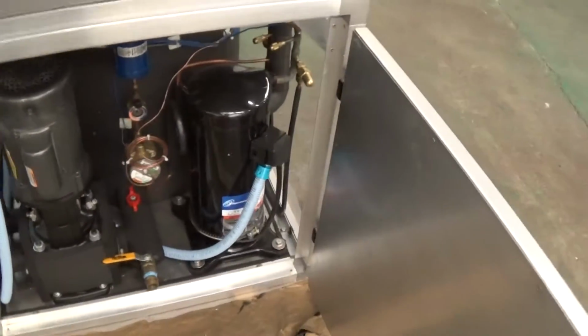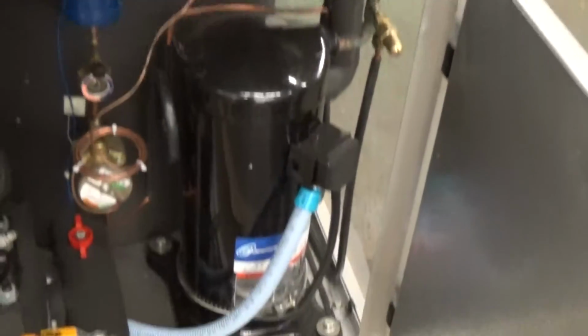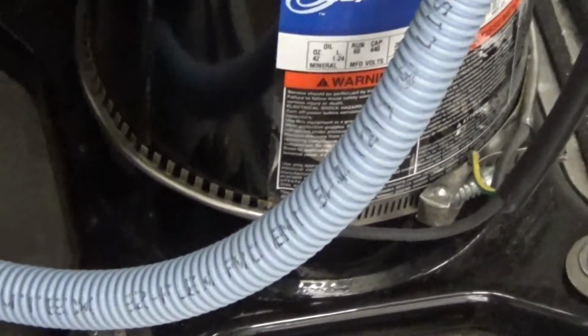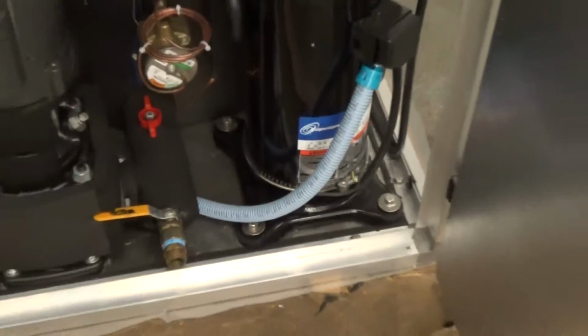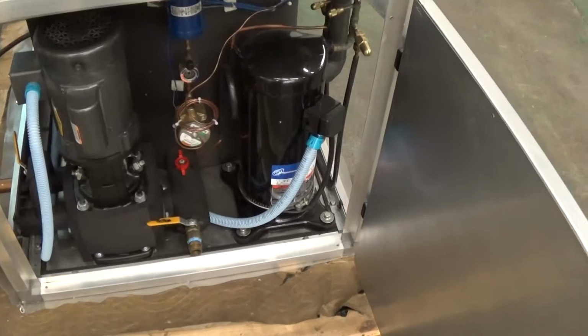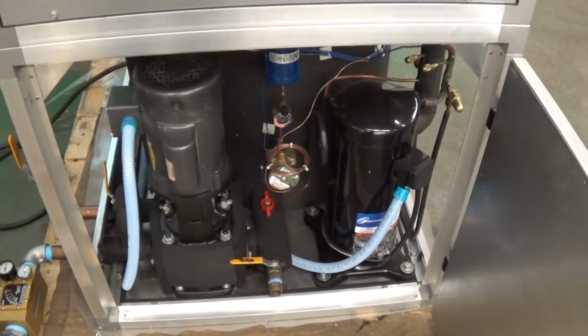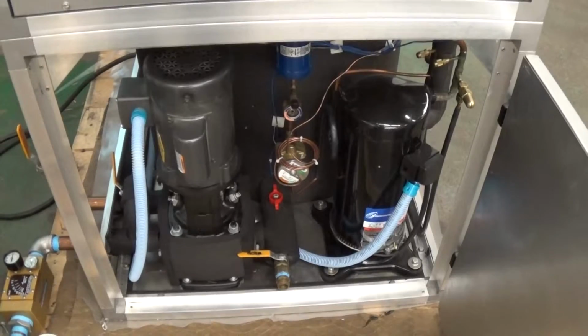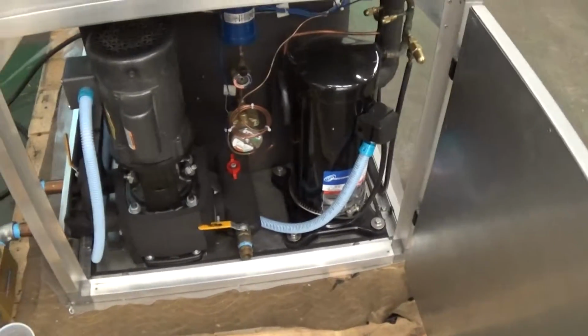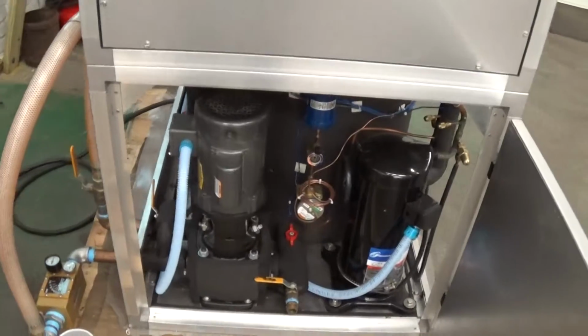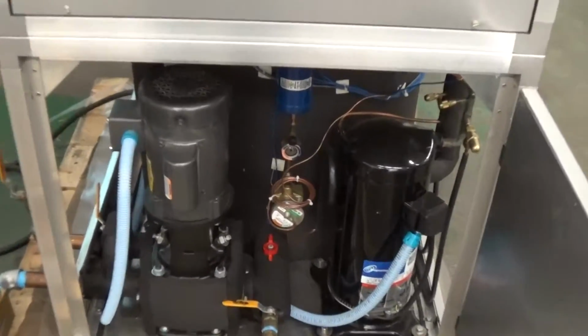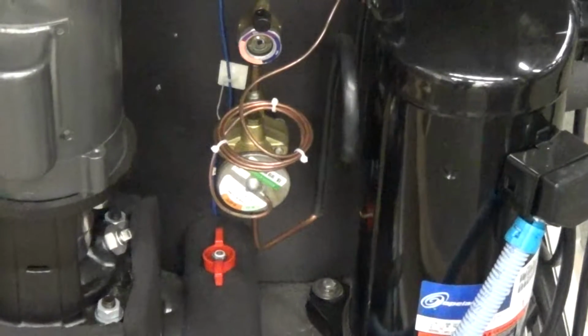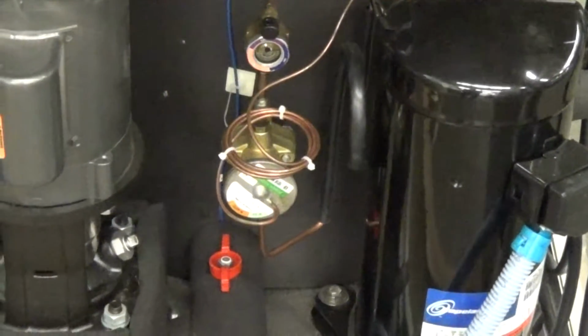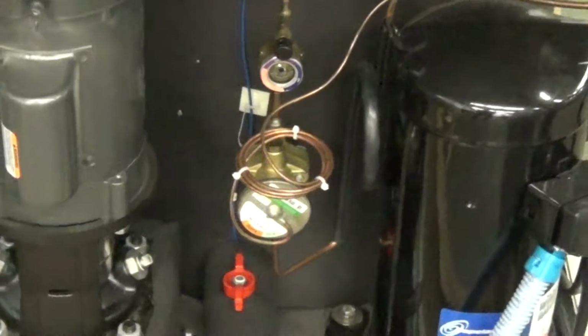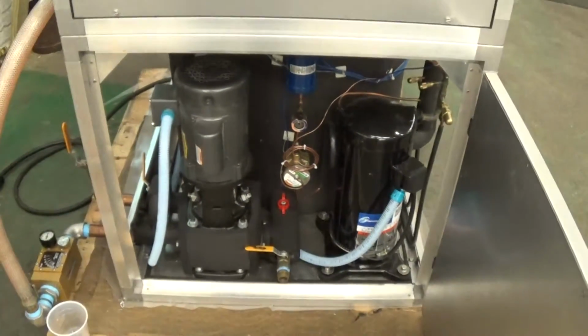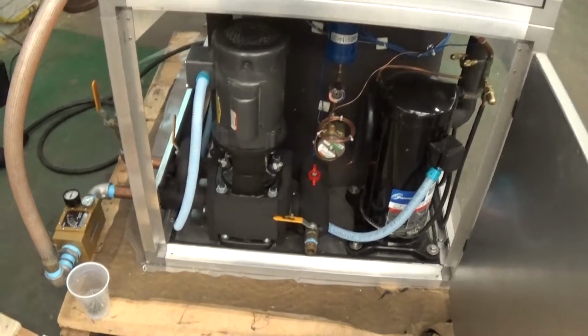You have your 3 horsepower Copeland scroll compressor here, and that has a heater band on it. As long as there's power to the unit, and you always should have power to the unit, that heater band's going to be on. And so when the chiller's turned off from a set point standpoint, that compressor heater will always be on, keeping that refrigerant nice and warm in the bottom of the unit. That's your thermo expansion valve. And above that is your refrigerant sight glass, which can be used for troubleshooting in case you ever think there's a refrigerant leak down the road.